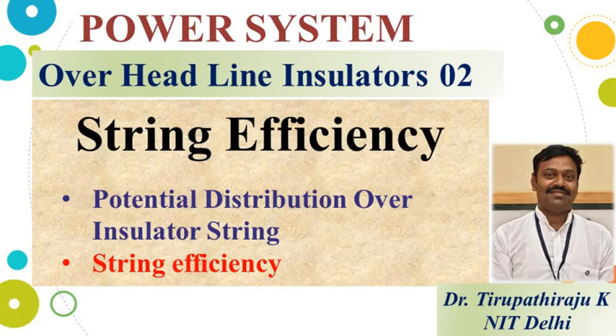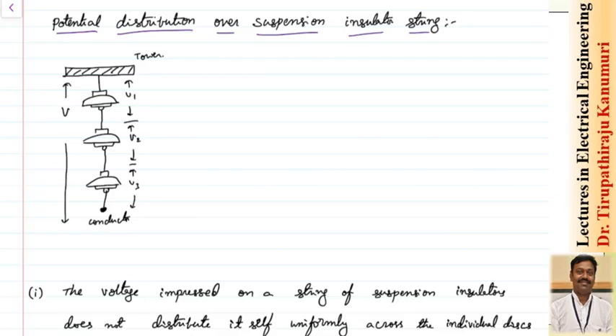Hi all, today we are going to discuss string efficiency. We know that if you are going above 33 kV, the pin insulators will not be efficient. So we go for suspension insulators. They are called suspension insulators because the insulator suspends from the tower. That means they are oscillating or hanging from the tower.